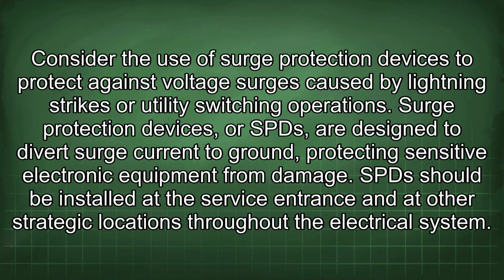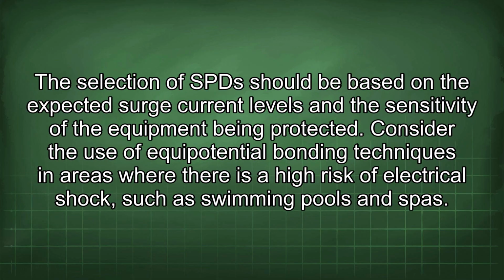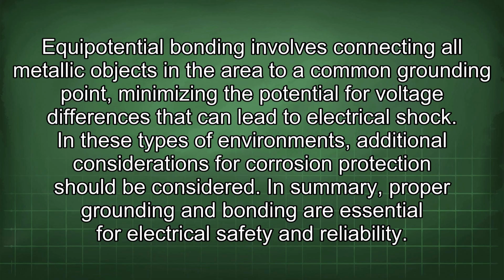Consider the use of surge protection devices to protect against voltage surges caused by lightning strikes or utility switching operations. Surge protection devices, or SPDs, are designed to divert surge current to ground, protecting sensitive electronic equipment from damage. SPDs should be installed at the service entrance and at other strategic locations throughout the electrical system. The selection of SPDs should be based on the expected surge current levels and the sensitivity of the equipment being protected. Consider the use of equipotential bonding techniques in areas where there is a high risk of electrical shock, such as swimming pools and spas. Equipotential bonding involves connecting all metallic objects in the area to a common grounding point, minimizing the potential for voltage differences that can lead to electrical shock. In these types of environments, additional considerations for corrosion protection should be considered.